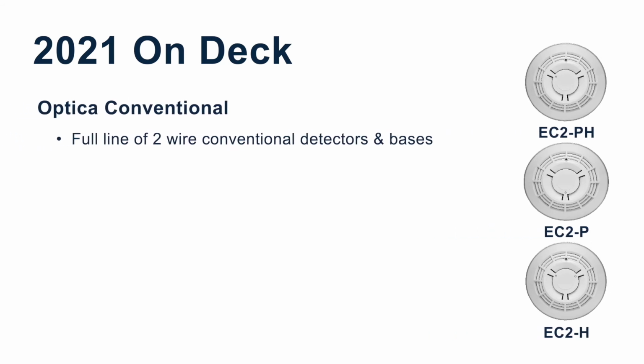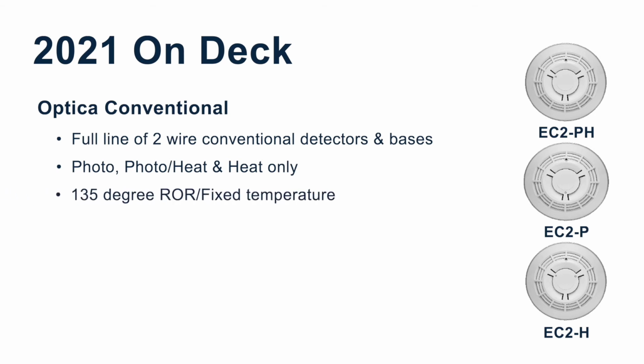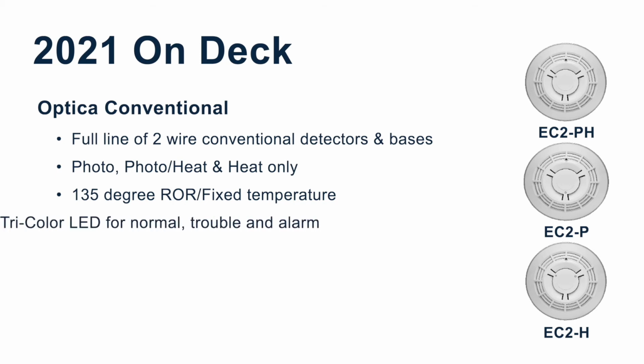Next in my list is the conversion of our Optica technology to a conventional detector series. This new line of conventional detectors will use the same sensing technology we used in the signature versions, but will communicate using a 2-wire conventional method. 3 detectors will be introduced along with bases. They will be a photo only, a photo with 135-degree heat, and 135-degree heat only. The smoke detectors will have the same nuisance resistance characteristics as the intelligent versions, along with a drift compensation, and will have a tricolor LED for normal, trouble, and alarm.